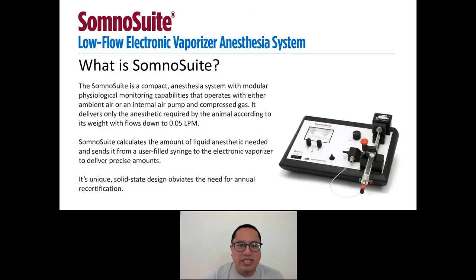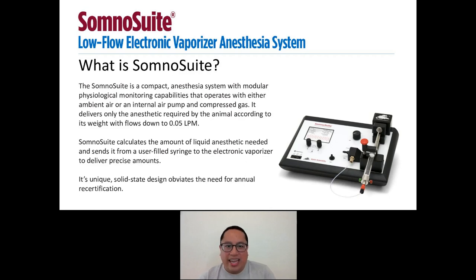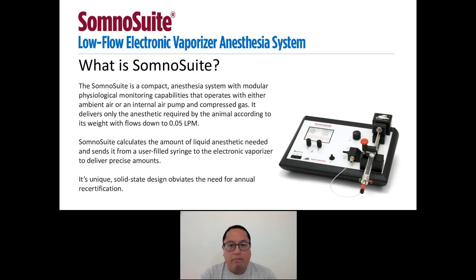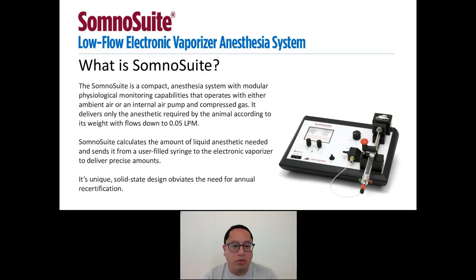So what is the SomnoSuite? The SomnoSuite is a compact low flow anesthesia system that uses a precision pump to deliver precise amounts of anesthesia. Measuring 11 inches length by 8 inches deep and 3 inches high and weighing about 4 pounds, the system is light and portable, allowing you to set it up on a bench top or in a hood.